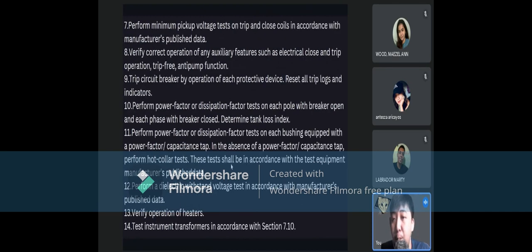7. Perform minimum pickup voltage test on trip and close coils in accordance with manufacturer's published data. 8. Correct operation of any auxiliary features such as electric close and trip operation, trip free, or anti-pump function. Number 9. Trip circuit breaker by operation of each protective device. Reset all trip logs and indicators. 10. Perform a power factor or dissipation factor test on each pole with breaker open, and on each phase with breaker closed. Determine tank loss index.